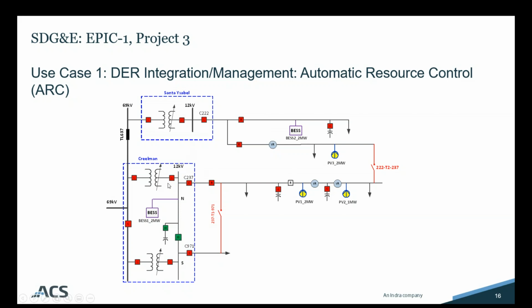And they have both existing devices, so they modeled all their existing devices, including load tap changer controls on each transformer, all the different reclosing and sectionalizing devices, as well as capacitors and voltage regulators, as shown here in the blue circles, as well as the added larger scale DER. So on the Creelman feeder, we have a 2 megawatt PV array, as well as a 1 megawatt PV array further down line. Also on Creelman, back at the substation, a larger utility scale 2 megawatt battery storage. Coming off the Santa Ysabel substation, the main feeder, we have a 2 megawatt PV array, as well as an additional large scale battery storage unit downline of one of the feeders coming off the Santa Ysabel.